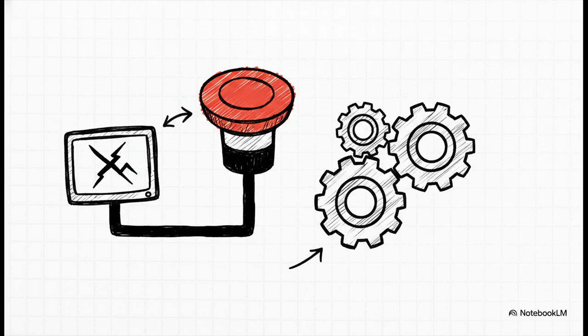But here is the really crucial point to remember. Software logic has its limits. When things get really bad, you need physical guarantees. The emergency jacking system uses direct wired switchboard push buttons that completely bypass the PLC logic altogether. On top of that, the physical 24-volt DC hardwired e-stop cannot be overridden by any computer glitch, network failure, or software freeze. No way. When you slam your hand on that button, you are breaking a physical circuit. The hardware takes over instantly, and the operation stops immediately.